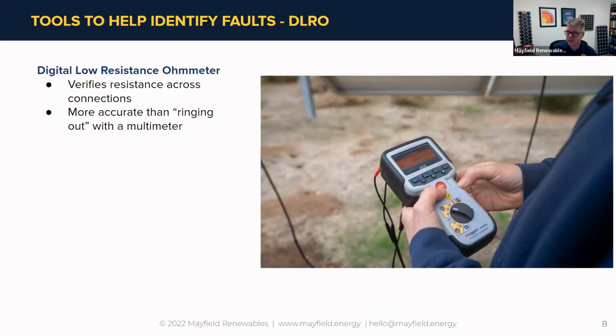Mike, do you have anything to add to that? Yeah, I wanted to make sure I got in that DLRO testing is 1 ohm or less. Think about your multimeter, it's not going to go there, not into the micro ohms. So we're below 1 ohm when doing this kind of testing, and for repeatability we need a test and measurement unit that will go down into those micro ohm areas. As for connectors, stay tuned. Not going to tip the hand, but we're looking at this with the connector manufacturers, and we think it's a viable option to help technicians make this test very quickly.